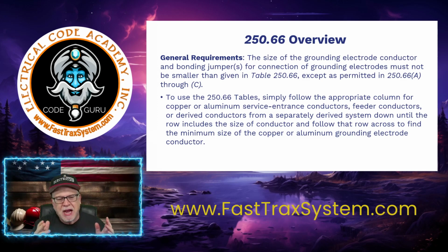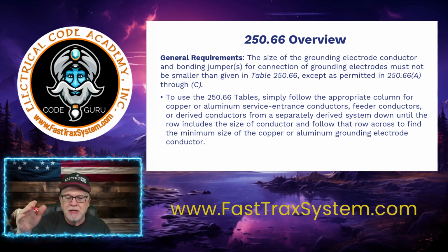Now, keep in mind that when we're talking about like a remote distribution panel that's in a detached structure, then you will still have a grounding electrode conductor. The only difference is at that detached structure, it's not going to connect to the grounded conductor. It's going to connect to the equipment grounding conductor terminal bus. Because you remember, the neutrals and the equipment grounds are separated at a detached structure. Okay, or remote panel. So we're really talking at the service, we're really talking about the grounding electrode system for the service. That's really the focus on today's topic.